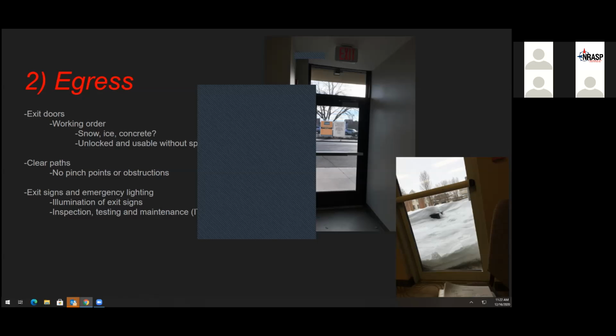Exit signs and emergency lighting are a big factor in our egress. The fire code states that all exit signs require illumination. Now they can be illuminated internally or externally. Some of the older buildings may have paper signs. There are even some glow-in-the-dark signs that do meet the requirements for illumination because they can hold the light for a long enough time.